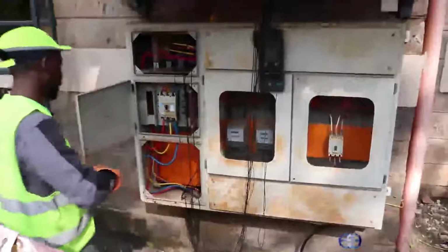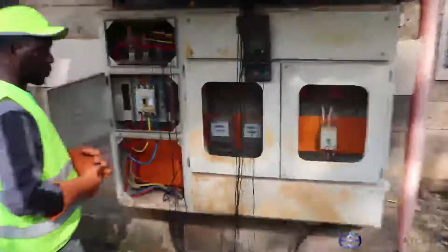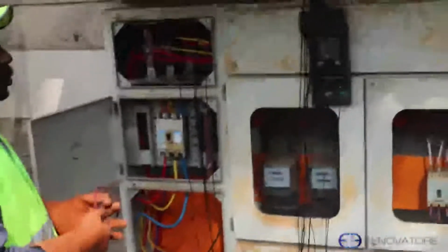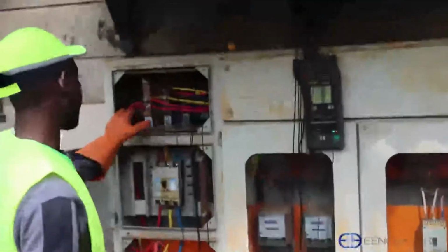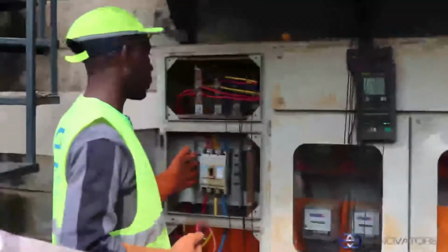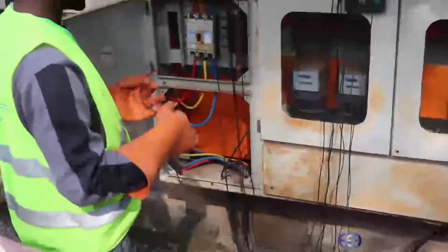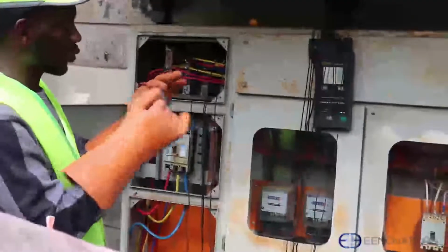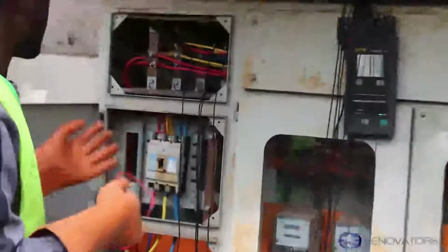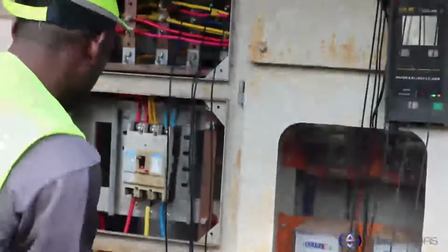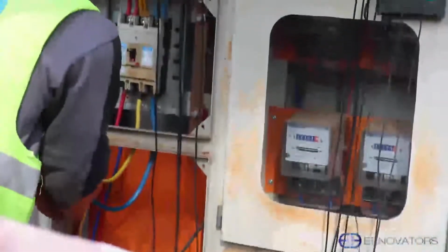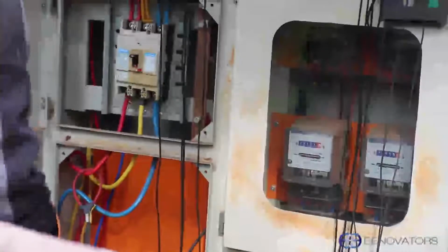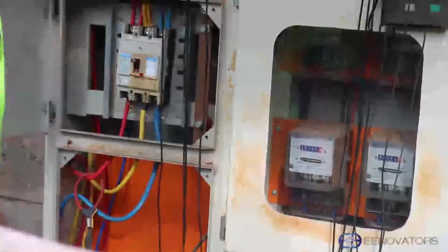So it implies that the direction of the load is going up, because the loads are at this point, the breaker is at this point, and the source of my power is coming from this bottom side. So if I want to wrap my CTs, I have to point my direction of current in the upward direction, because my loads are on the top side of this breaker.